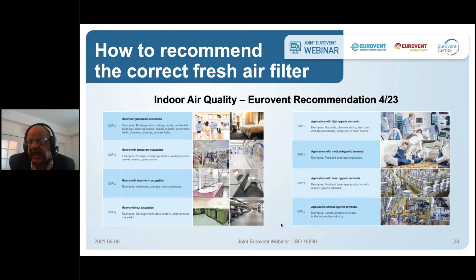Now the filters get nicely tied up with the outdoor air quality and indoor air quality, a tool to select the correct filter with the right pressure drops and the right amount of energy spent because of the pressure drop in the filters. They reflect different values going from the everyday filter to the highest quality and highest priced filter, showing the energy efficiency difference. That's going to be very helpful going ahead in keeping filtration levels and energy efficiency together.